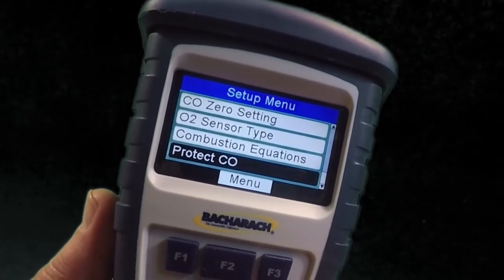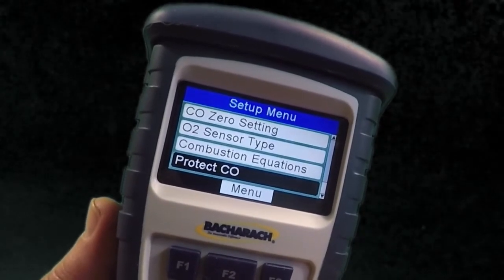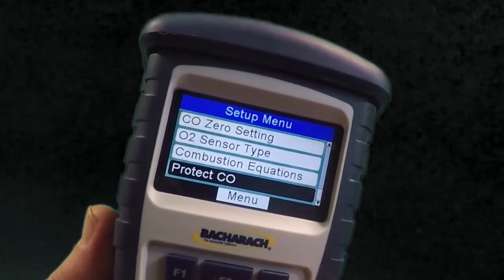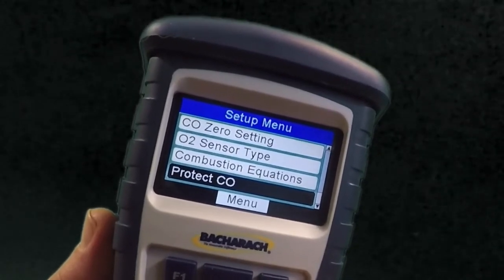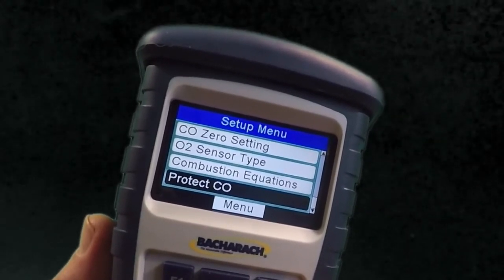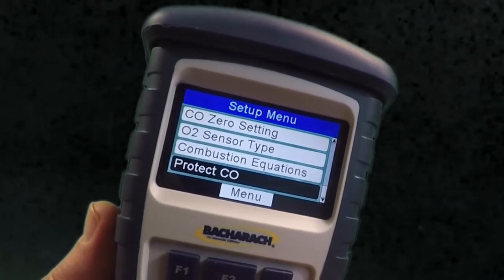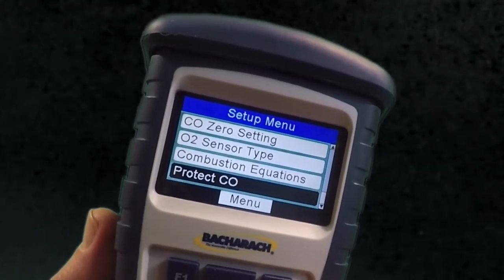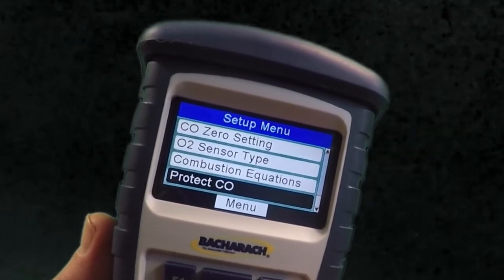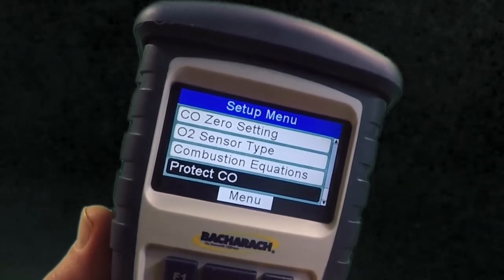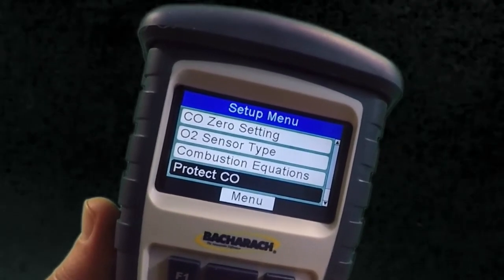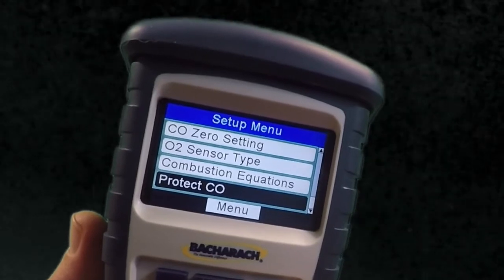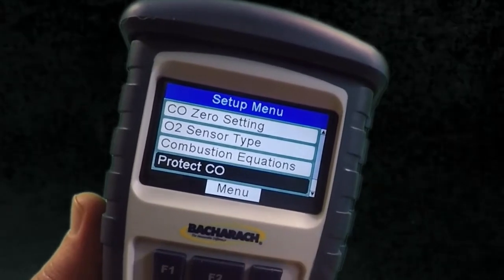Protect CO, the default is 500 ppm. What that does is it shuts the pump off if the CO reading reaches 500 ppm. This is to protect the CO sensor from damaging levels of carbon monoxide. I might set it a little higher. It's not unusual to get a bump over 500 ppm, particularly on a cold light off, but do keep in mind the more CO the sensor is exposed to, the shorter its life will be.